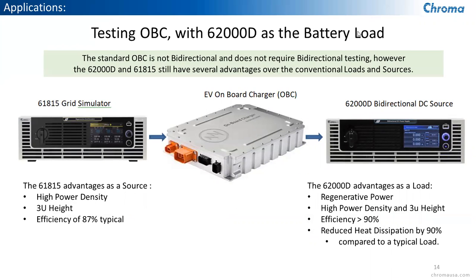So a little more about OBC testing. Even if it's not bidirectional, there's still a great advantage to using the 62000Ds. When they're used strictly as a load, simulating a battery being charged from your onboard charger, it still is greater than 90% efficient versus a standard conventional load. It has that small 3U compact high density power packaging, and it reduces the heat in the air in your facility by 90% versus what you'd be producing with a conventional load. You also can use our grid simulator, which is a great high density power 3U package, to give you 87% efficiency using it as an AC source simulating the grid.